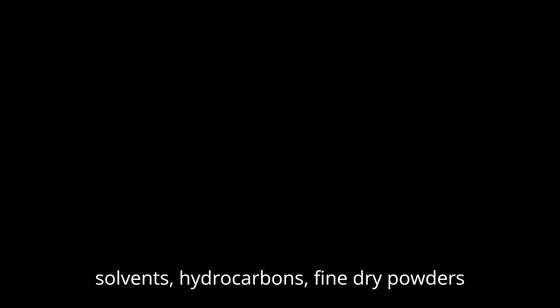But now, think about the opposite end. Materials like oils, many solvents, hydrocarbons, fine dry powders like flour, or even thick layers of foam. They have low dielectric constants. Very low. Sometimes down in the range of 1.5 to 3 compared to water's 80. Big difference. Huge. These materials tend to absorb or scatter the microwave energy instead of reflecting it cleanly. The result is a very weak echo, sometimes so weak that the transmitter struggles to distinguish it from background noise.